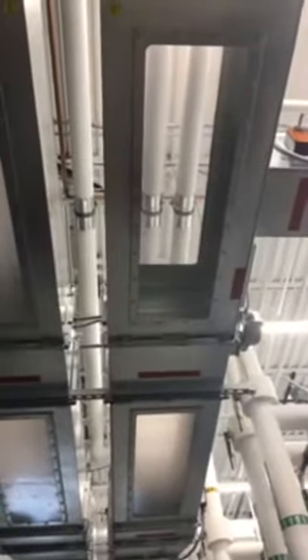Now what Paul did while I was talking was he cracked open a bleed damper. This is going to allow us to bring in some fresh air to ventilate the space, to mitigate the smoke. This is something that might be done in a stairwell pressurization, for example. Smoke management, giving occupants a safe means of egress to leave the building. So you can see, just within a few seconds of introducing some fresh air with a working fire smoke damper on system 1, the area after the damper is clear of smoke, right?